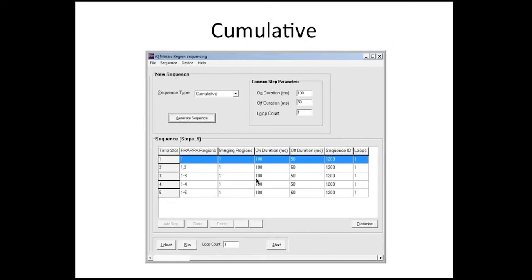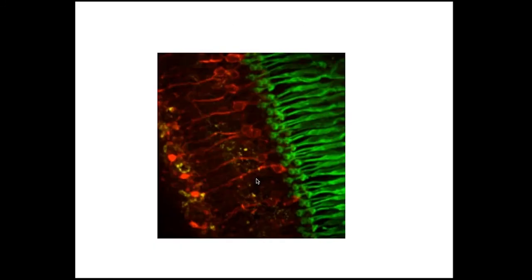The next mode is cumulative, so it's a little bit self-explanatory. You can set up in the sequence window that if you look at sequence steps 5 and go down the list, we're going to start with 1, then 1 and 2, 1 through 3, 1 through 4, and 1 through 5. This would give you the ability to do maybe an IV curve with your optogenetic probe.